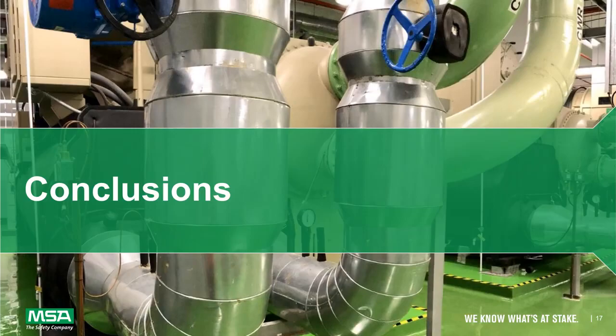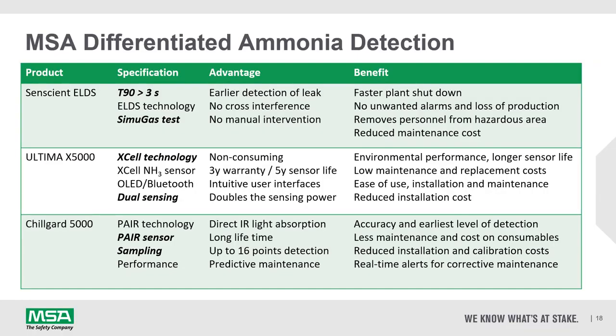So to conclude, there are a number of different ammonia sensing technologies available, of which we have discussed just 3 of them here today. One being the open path device, which has a fast speed of response of less than 3 seconds and an auto test facility. Electrochemical cells with extended life and non-consumable sensing elements, and the ability to have 2 detectors wired into 1 transmitter. And finally, a multi-point detection system using an acoustic infrared technique, reducing the cost of cabling and the number of sensors that need to be recalibrated in the field.